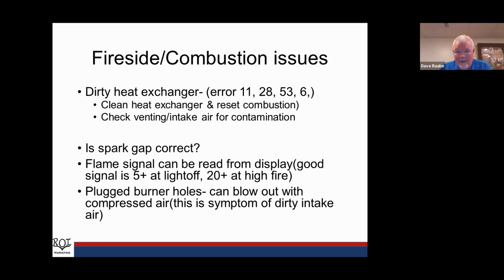Another thing we could run into on the fire side is the spark gap, correct? So we need to check our spark gap and make sure it's what it should be. And the nice thing with our boilers, we can actually read the flame signal right out of our display. I don't need to put a meter on it. And it reads in microamps. What I've found is a good signal is going to be higher than a 5 at light off. And then as that boiler gets up to high fire, it should be 20 plus. I've seen them in the 30s, low 30s at high fire.